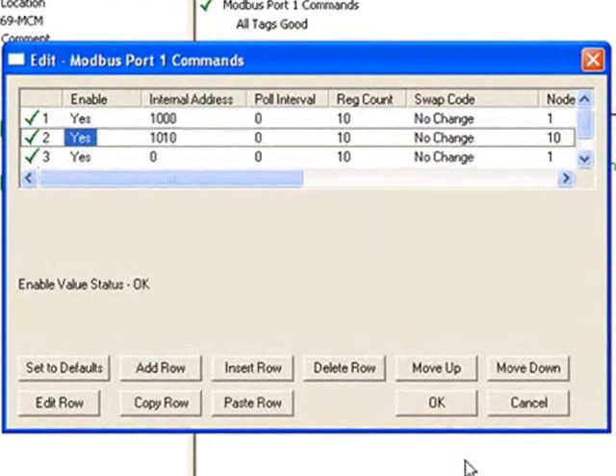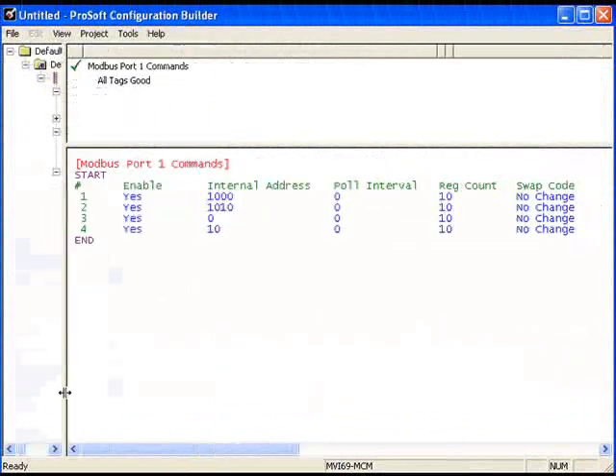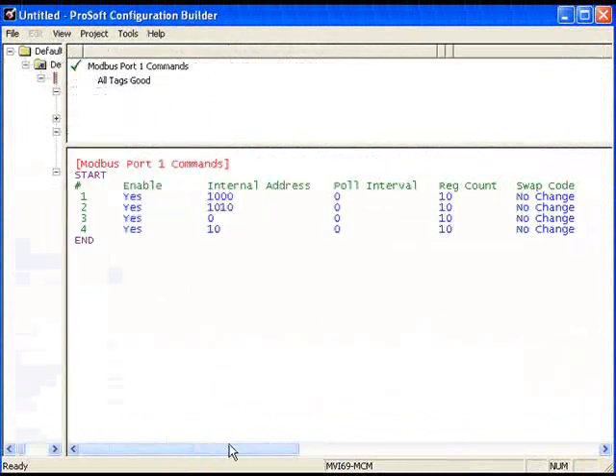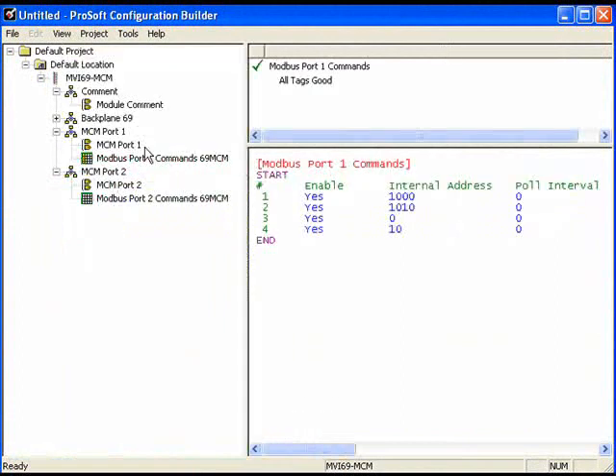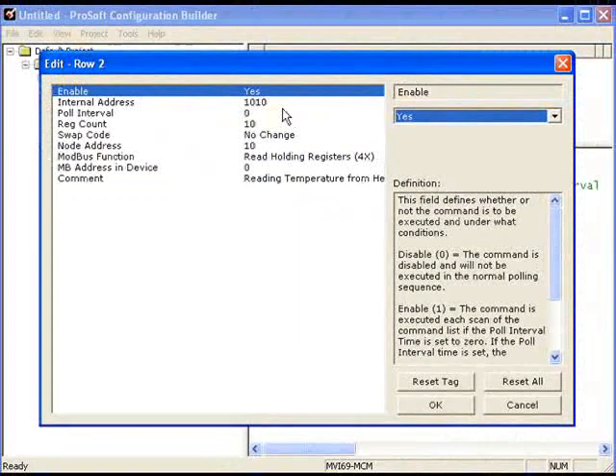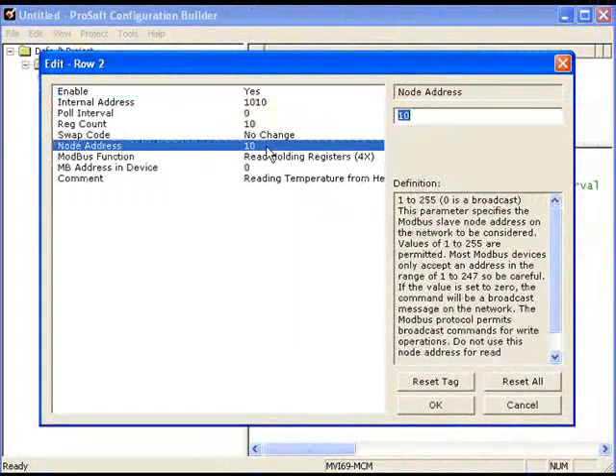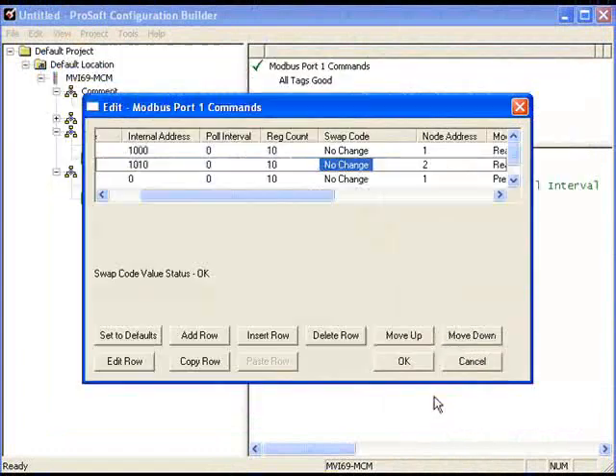Now we can look at the module configuration for port 1 Modbus commands, which shows a summary of how the commands are laid out. I notice I made a mistake — I put node address 10 and I want to make that node 2. So I'll go back into Modbus port 1 commands, double-click on that command, change the node address to 2, and click OK. Click OK again.